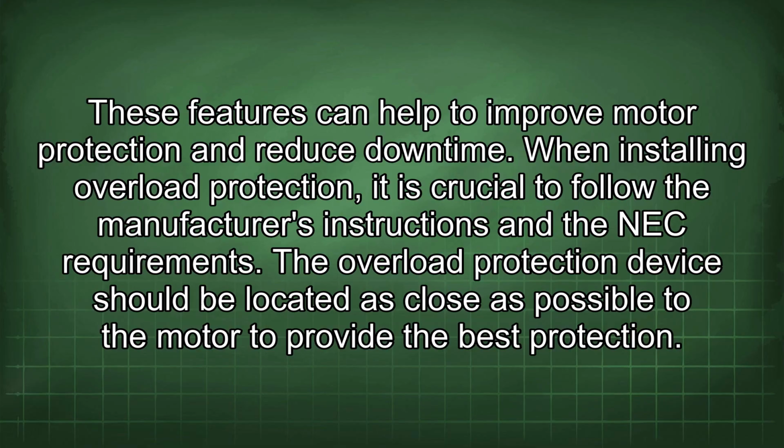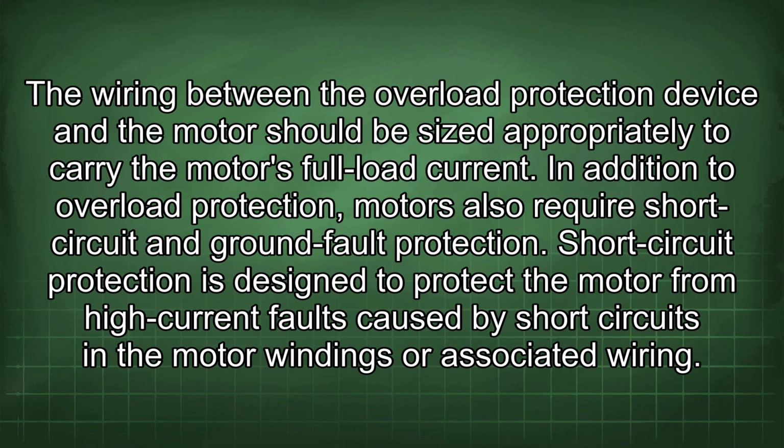When installing overload protection, it is crucial to follow the manufacturer's instructions and the NEC requirements. The overload protection device should be located as close as possible to the motor to provide the best protection. The wiring between the overload protection device and the motor should be sized appropriately to carry the motor's full load current. In addition to overload protection, motors also require short circuit and ground fault protection.